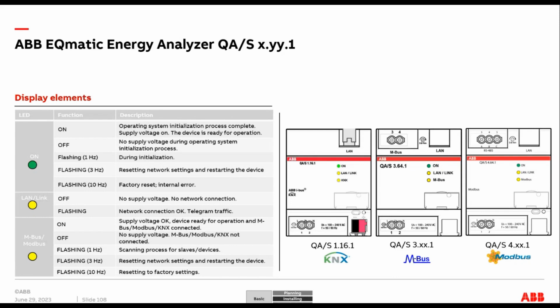If the green light is on, the system is fine, it's working, everything's okay. If it's flashing at 1 Hertz, it's initializing when we first power up the device; it will flash like that for about a minute while the device powers up, gets its IP address, sets itself up on the network, checks everything internally, and then it will be ready. If it's at 3 Hertz, we're resetting the network settings and restarting the device. If it's at 10 Hertz, we've just done a factory reset, or possibly we have an internal error with the device, something else to be aware of. The LAN links are quite obvious: if there's no activity on the LAN, the LED's on. If it's flashing, there's activity on it.